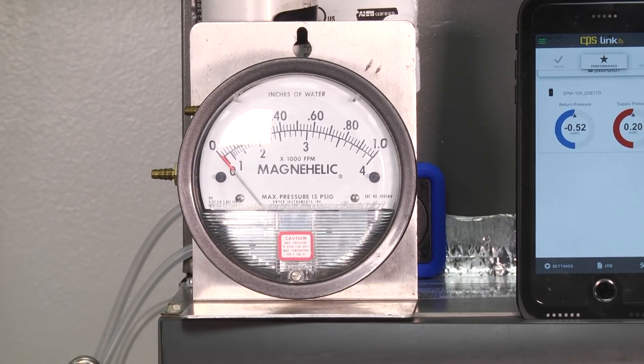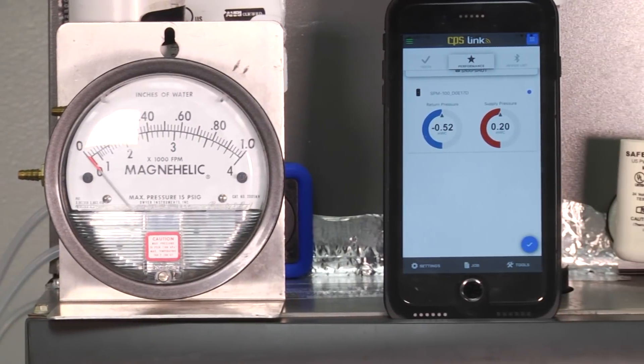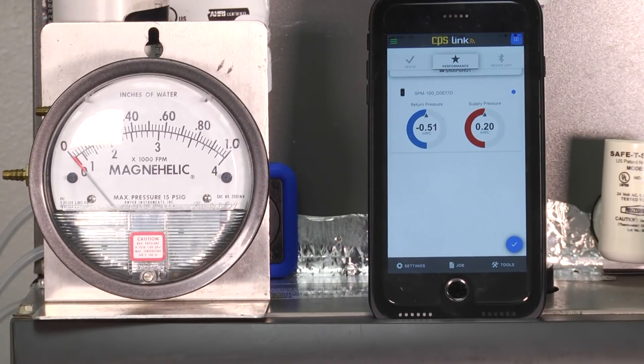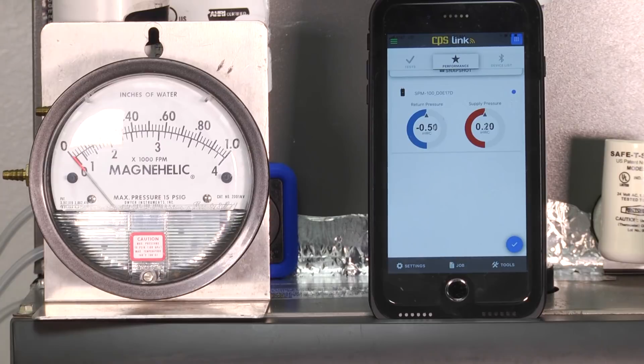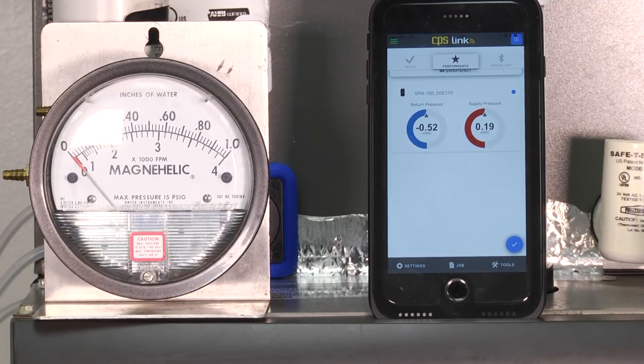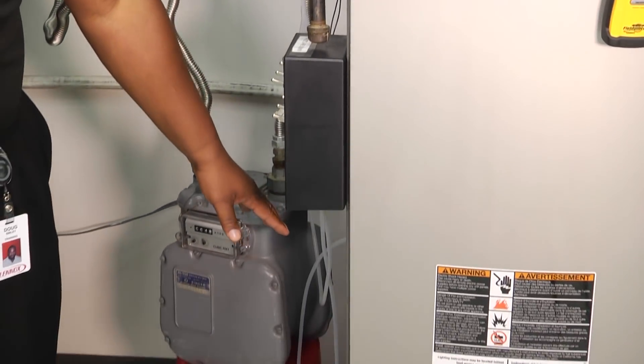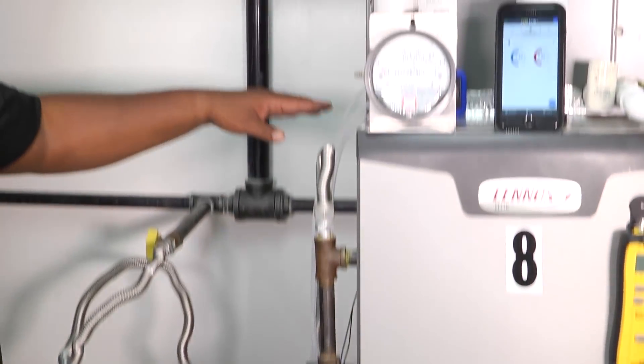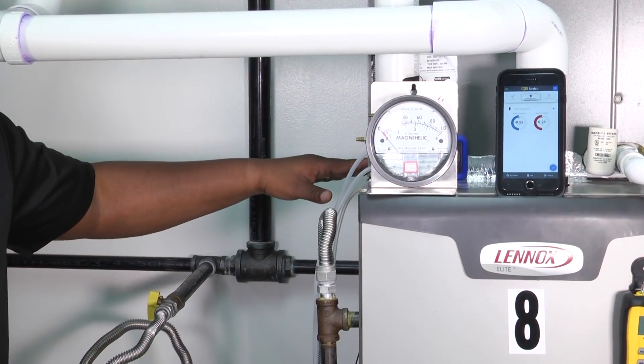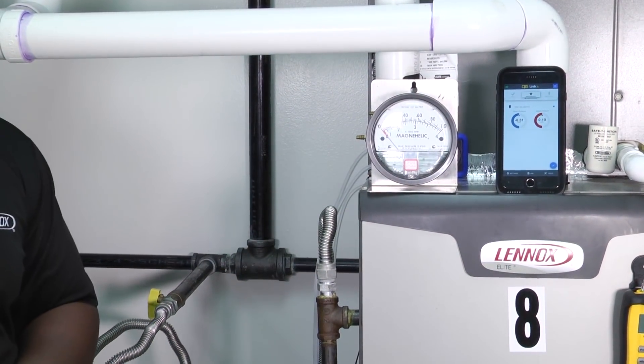Now we've got our static pressure readings going on our system. A couple things we can do: when we take these two and add them together, this gives us our total static pressure. We need both the reading from the return side and a reading from the supply side to get the total. We're inserted right after the filter but before the blower, and then right before we get to our coil to take that measurement.